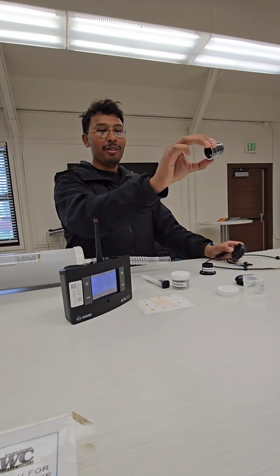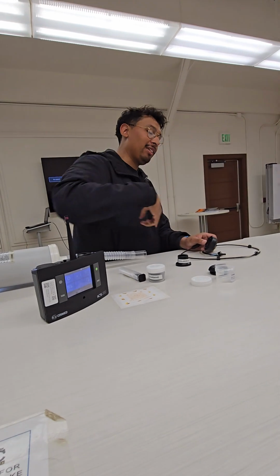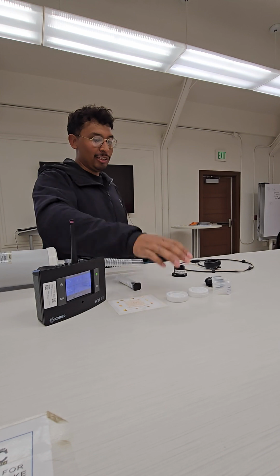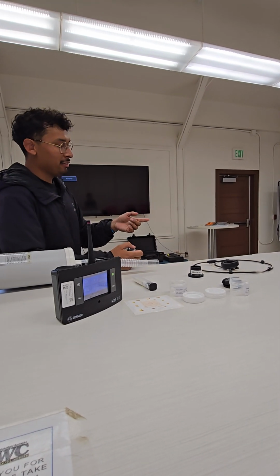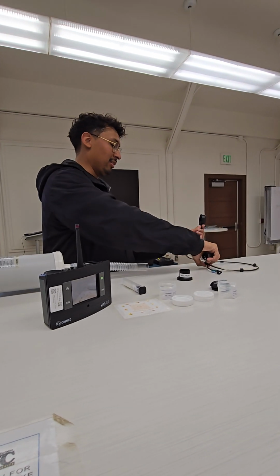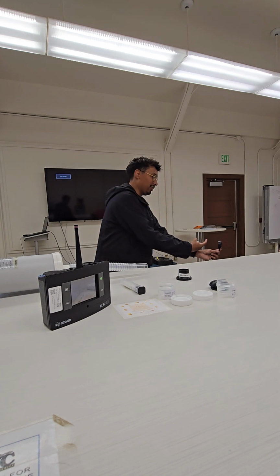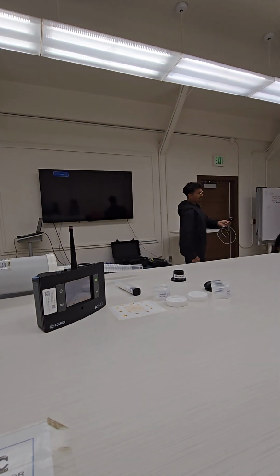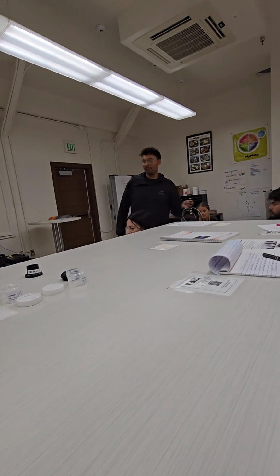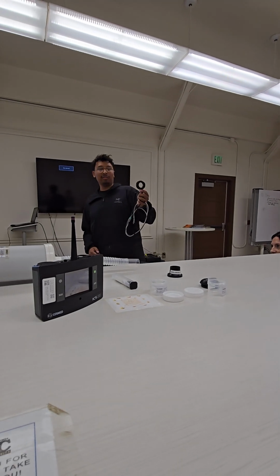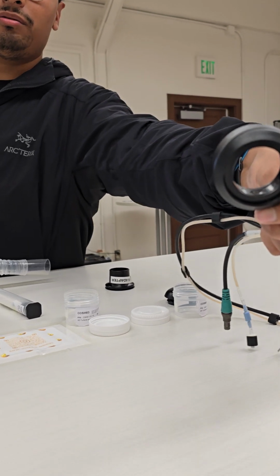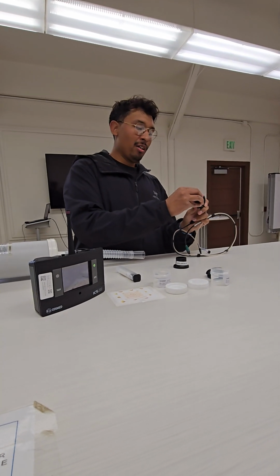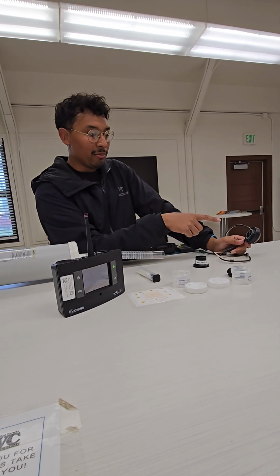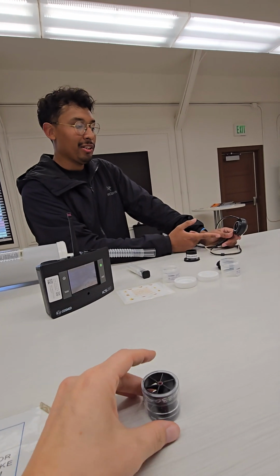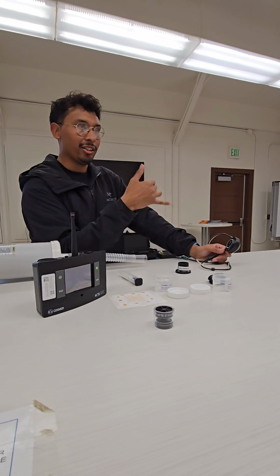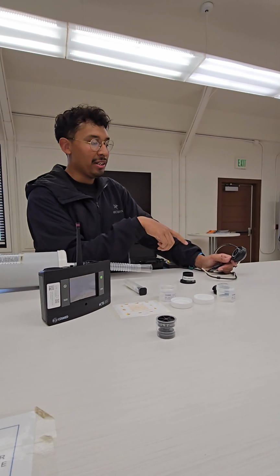So basically, this turbine, I'll pass it around. It has a little filament in the center that spins in different directions. So when someone is breathing out or breathing in, it'll spin one way or the other. The optoelectronic reader, and I'll show you guys, has little sensors on the inside of the ring. Whenever you place the turbine inside of it, depending on if they're inhaling or exhaling, the turbine will spin one direction or the other. The sensors are disrupted, and basically they can detect which way it's turning. So if they're breathing in, they're breathing out, and then how often.